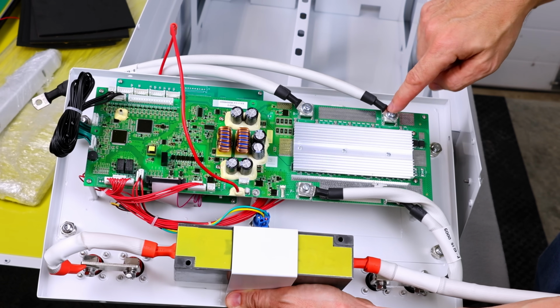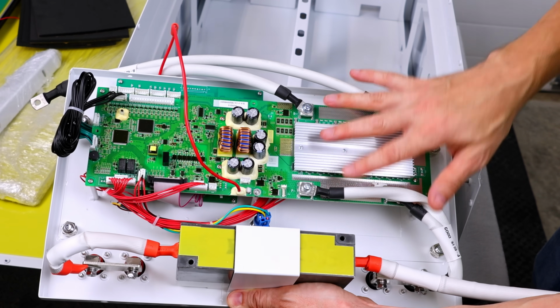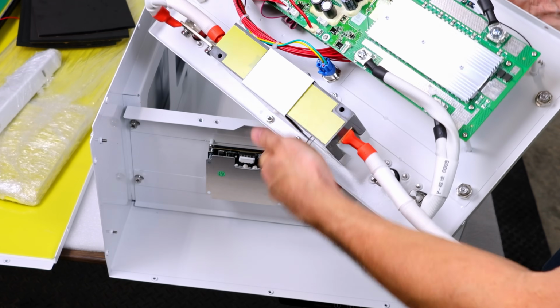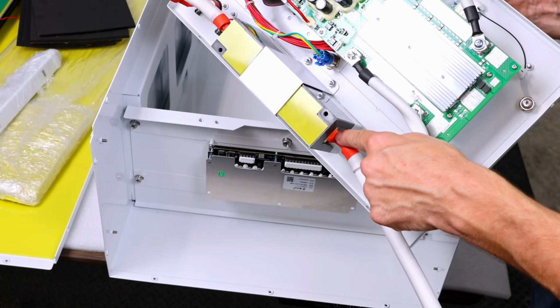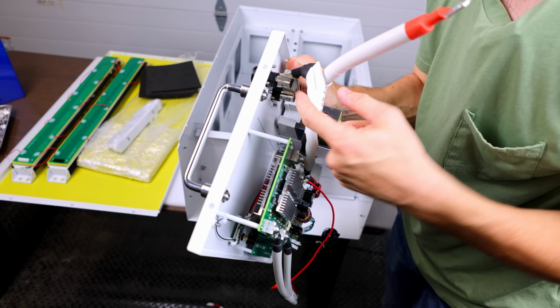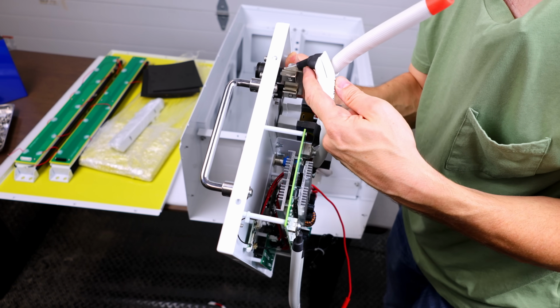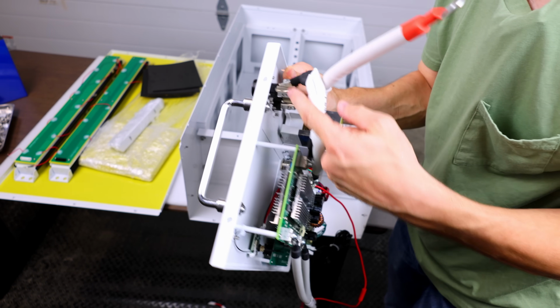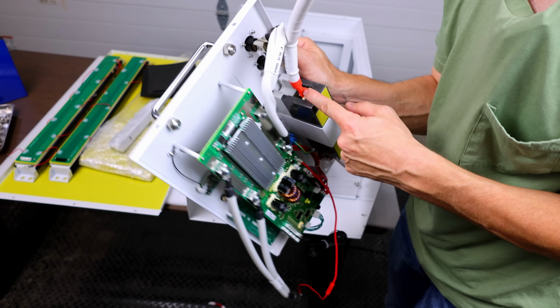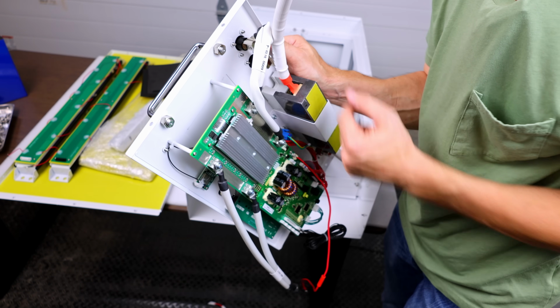These are torqued down without any insulation under them. That looks good. However, here on the breaker, it looks like some insulation has been trapped. I don't know if you can see that, but there's a tiny bit of insulation trapped under that screw. So I'm gonna have to disconnect all of these and trim the insulation back and reconnect them.